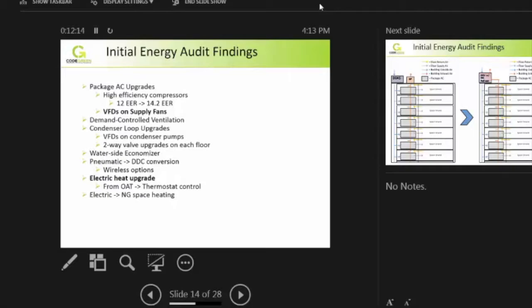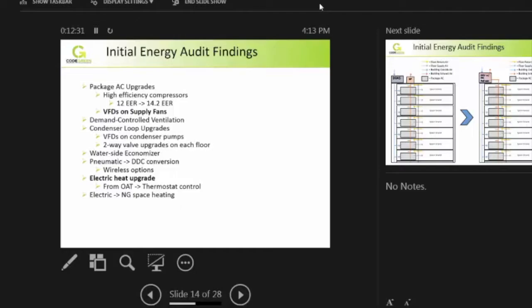We also looked at demand-controlled ventilation. Looking at this layout, there's a dedicated outside air system delivering air to each floor with modulating dampers on each floor, so tying in CO2 control on each floor was a more affordable possibility than with a lot of arrangements, so it made sense for us to identify that.